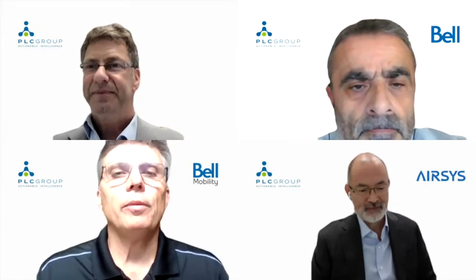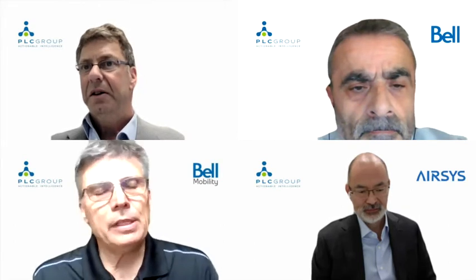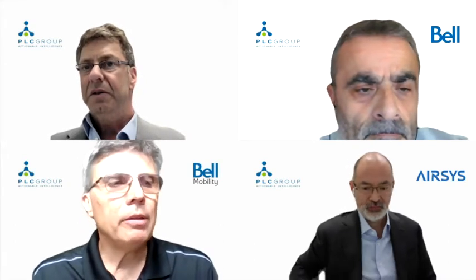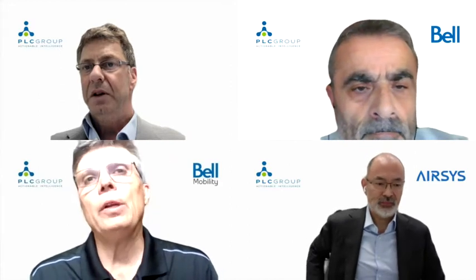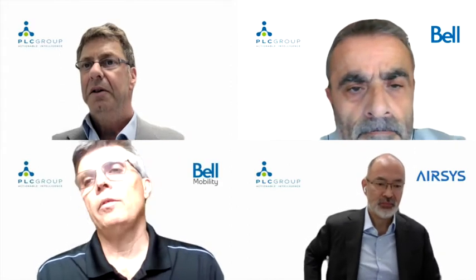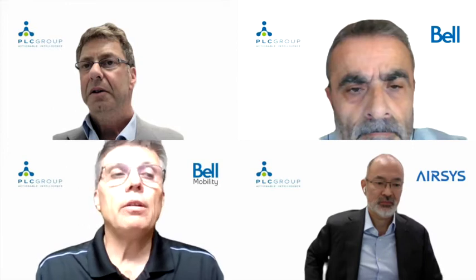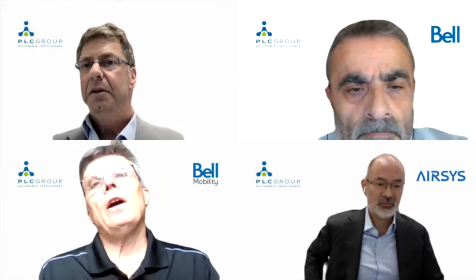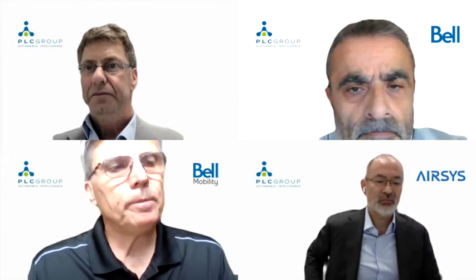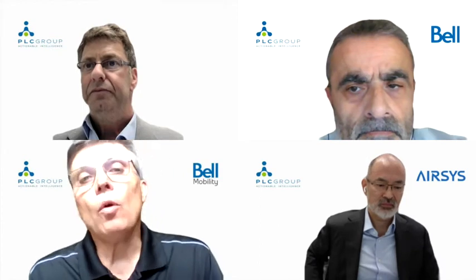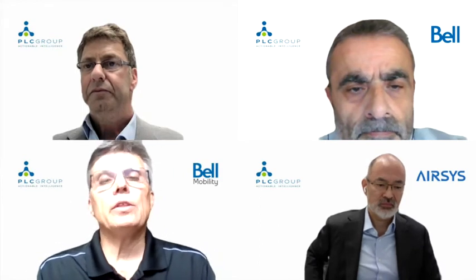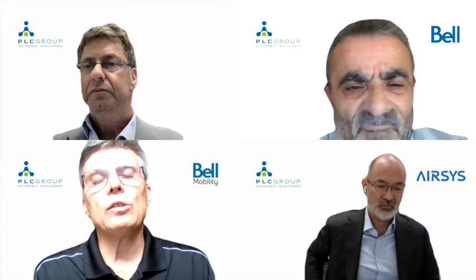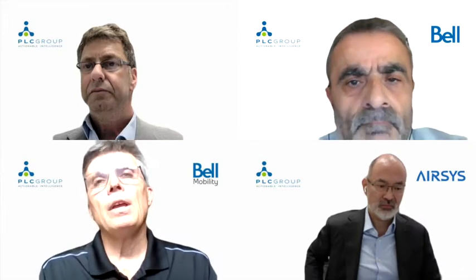Okay, wonderful. So my IEEE paper just opened up the discussion at a time when a lot of people were putting up two air conditioners on the wall for redundancy, and either disabling economizers or using them, or didn't know how they should be set properly. So it was an exploration into free cooling.